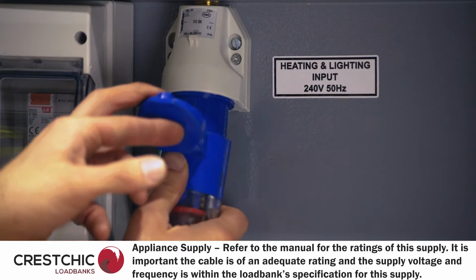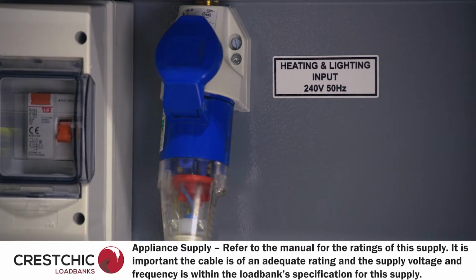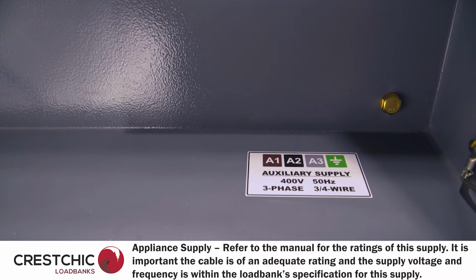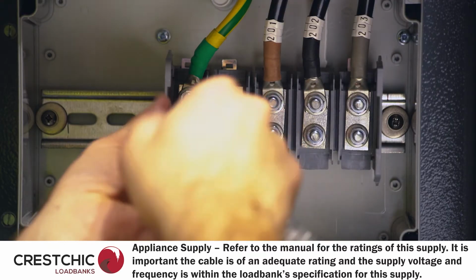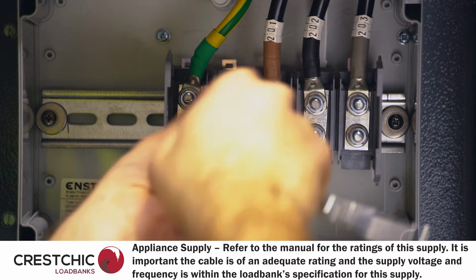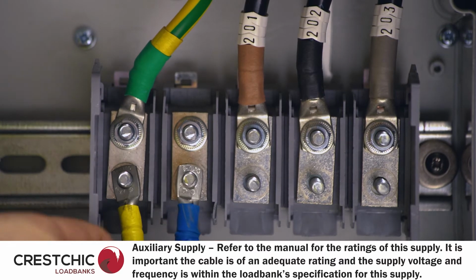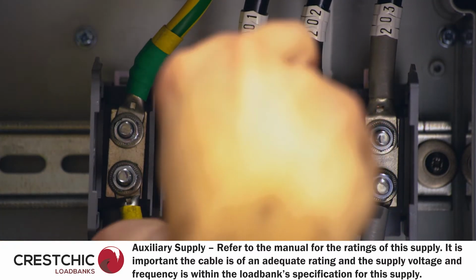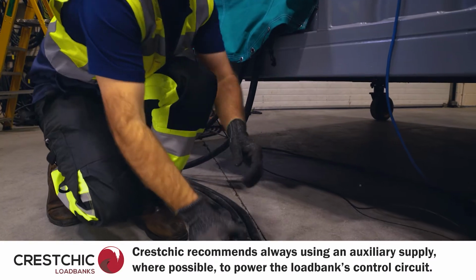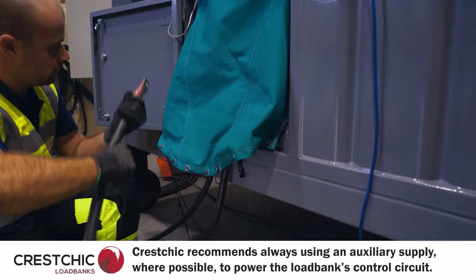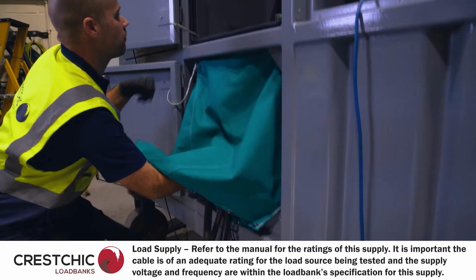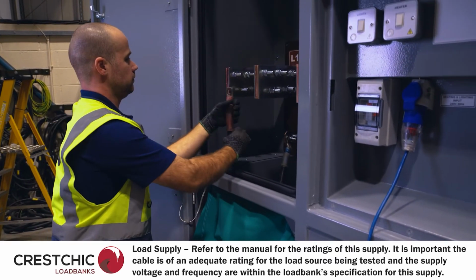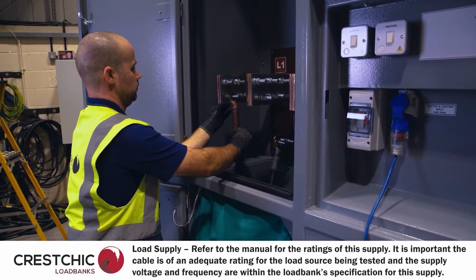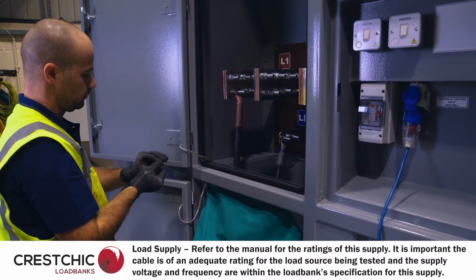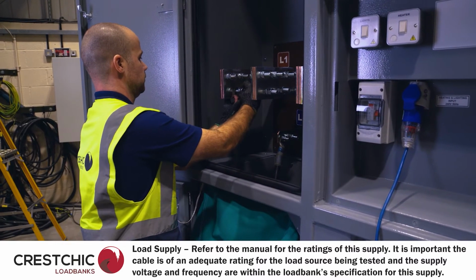We are now ready to start connecting cables to the load bank. As mentioned previously, there are generally three supplies. For the appliance supply and auxiliary supply, the cable for these supplies should be sufficient for the power being drawn. The load bank manual should be referred to for these details. The load supply connections should be sufficient for the quantity of power required. Therefore, the cable ratings do not have to be the full power ratings of the load bank.